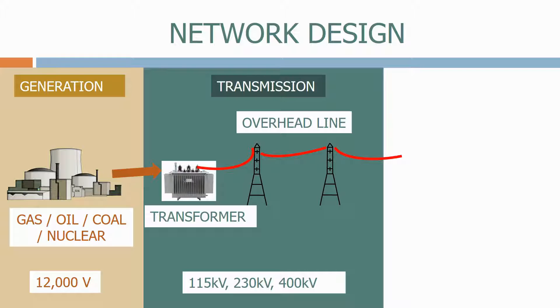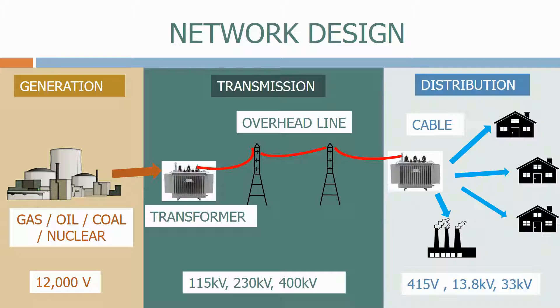Transmission systems use overhead lines. To allow the electricity to be transmitted over long distances we need to step up the voltage. We do this with a transformer. We step up the voltage to minimise the losses on the line and reduce the size of the conductor. The transmission voltage tends to be 115 kV, 230 kV or 400 kV.